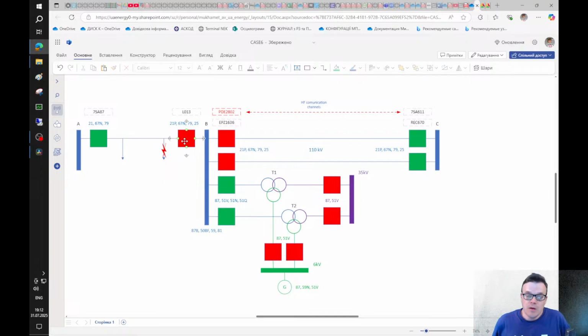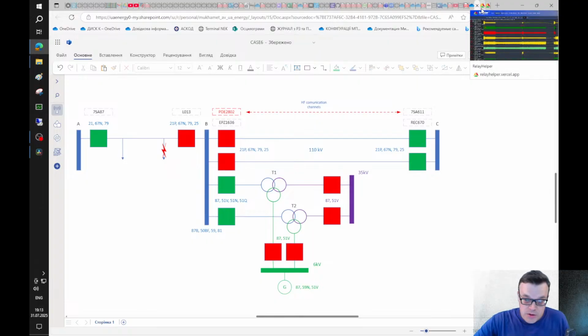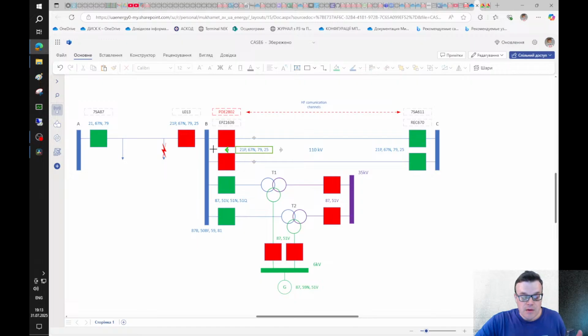We have a lack of information, because the staff from this power plant said that they could not download the record from this device. And the problem is that because this is a transfer bus circuit breaker, it was not connected to the digital fault recorder, so we don't see the exact currents from this line. But I'll show you what we did to find out what should work and prove that the problem is with the protection on this line.